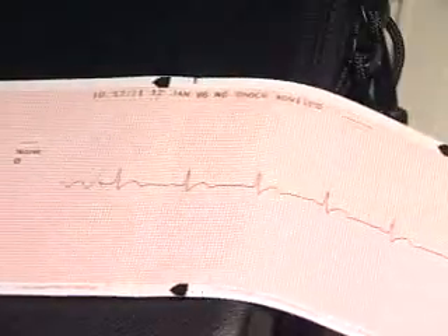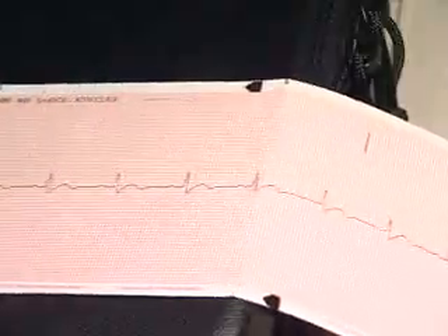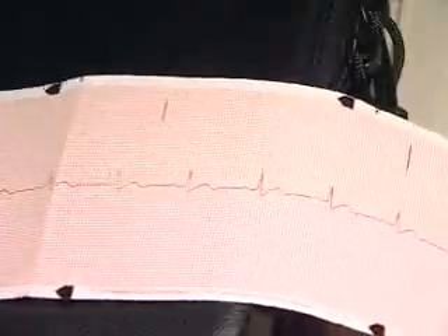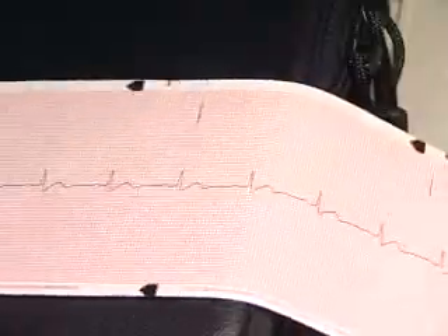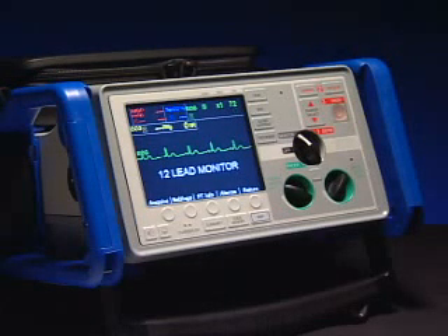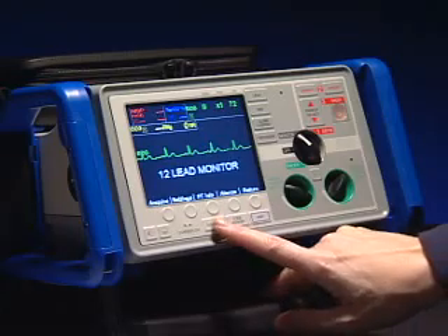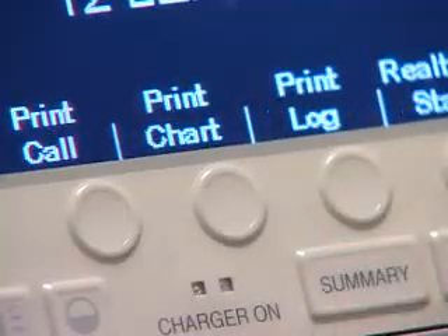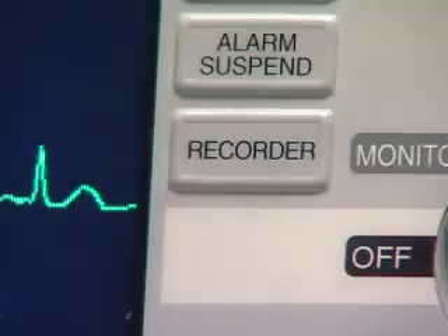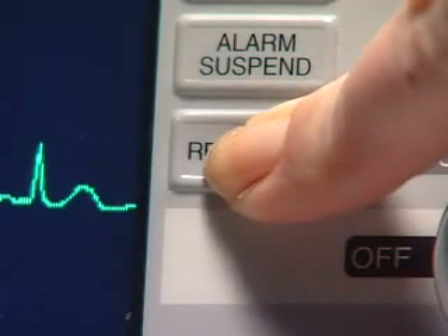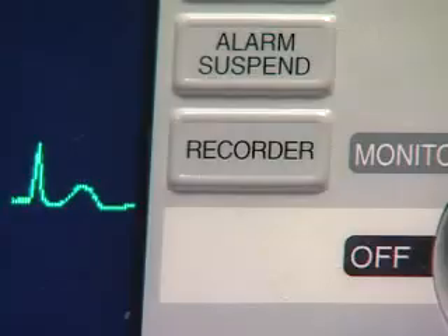The Summary Report can be configured for automatic erasure after power off with selection values of 5, 15, 30, 90 minutes, 6 hours, 12 hours, 18 hours, and 1.5 days. The Summary Report can also be erased manually at any time. To print the stored information, press the Summary button below the E-Series screen display. Then press the soft key to print a selected call, print chart, or print log. To stop printing a report, press the Recorder button or turn off the unit.